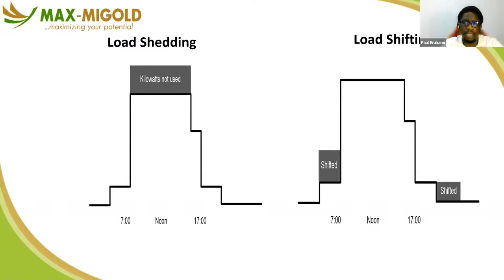So when some companies say 12 o'clock to 2 o'clock is break time, and we're shutting the chiller, shutting down all lights except emergency lights, they know what they're doing. Because that is the time when you have the peak load, but since we're on break, we want to drop that down drastically. That's called load shedding — cut it off, save it completely. Your peak drops, your total energy drops.